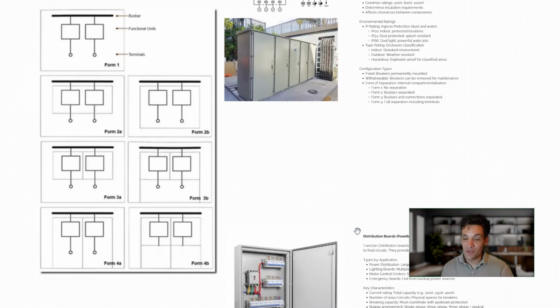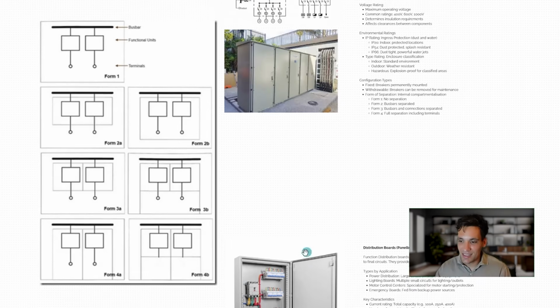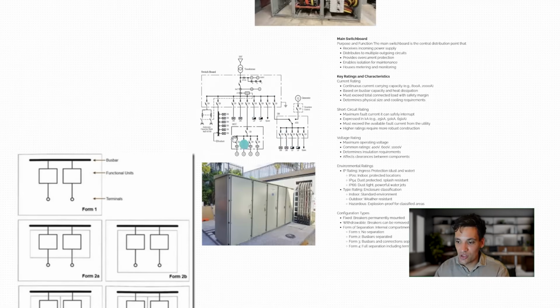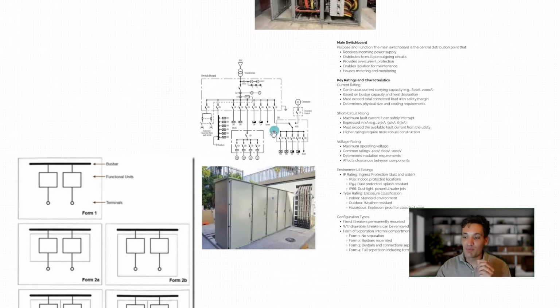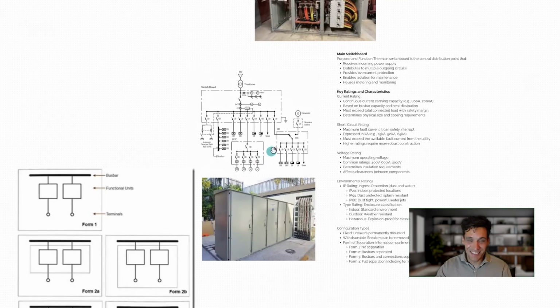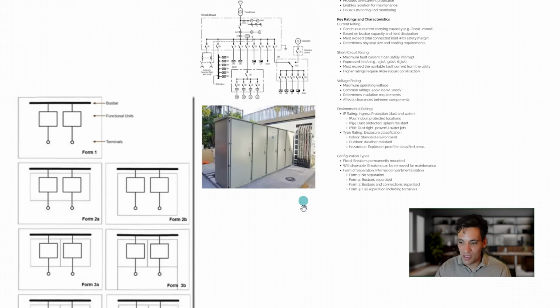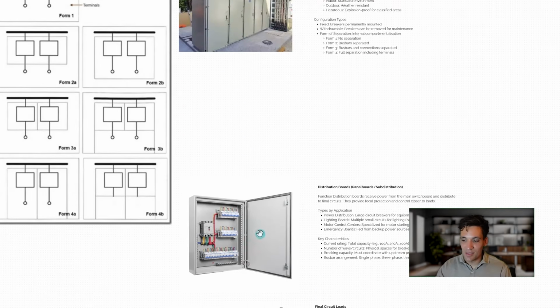On bigger facilities, you'll have a main switchboard, then cabling that connects directly to smaller distribution boards, which then connect to the separate loads. Again, only big loads, like maybe on a building, the lifts, big pumps, big HVAC units would be connected directly to the main switchboard. In other cases, you generally have sub-distribution boards which connect to all the lighting. So you might have like a 400 mil cable coming into your main distribution board. Maybe you've got like a 70 mil cable connecting to the sub-distribution board, and then to smaller circuits connected to that, you could have 4 mil, 8 mil, 16 mil cables.